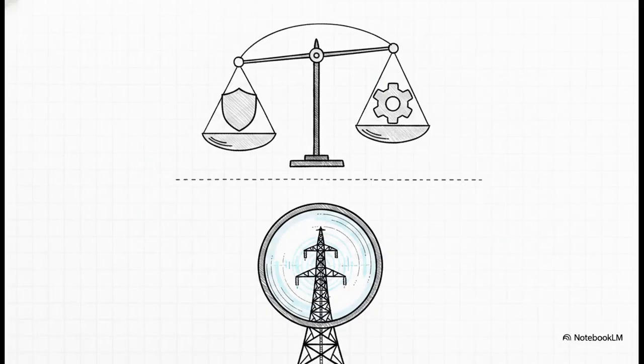So, wrapping this up, you might have started this explainer thinking protection is just detect a fault, trip a breaker. But in reality, it's that dependability versus security trade-off shaping every single setting decision. And more importantly, the physical accuracy limits of your CTs and VTs dictate what the relay actually sees. You simply cannot protect what you cannot accurately measure.